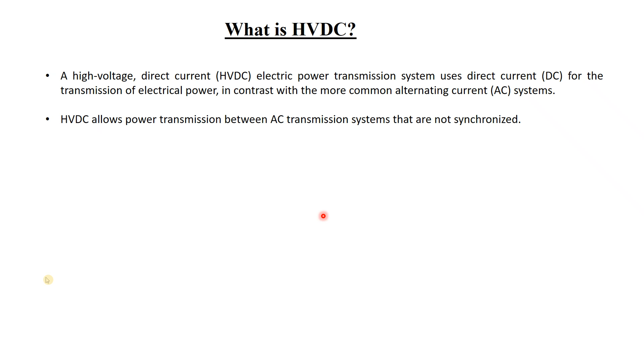But how can you connect DC with AC? You cannot do that directly. So the HVDC, after transmission, has to be converted into AC. When you convert it to AC, you are setting the frequency of your choice. Suppose it is 50 Hz in India and 60 Hz in the USA. If you are connecting to a 50 Hz grid in India, then using an inverter you just set 50 Hz and connect. That means the power does not have to be synchronized, because you are manually setting it to 50 Hz and then connecting it. So it is quite easy. Connecting any AC to AC is quite easy, and it is quite easy to connect DC with DC, and DC with AC, provided the DC is converted back into AC, and then it can be connected.